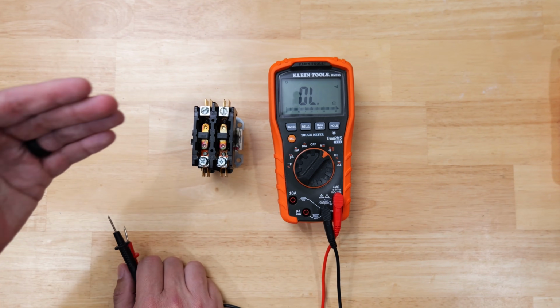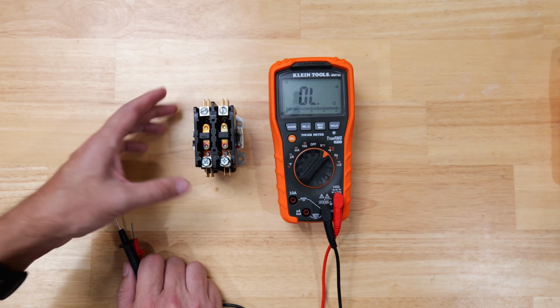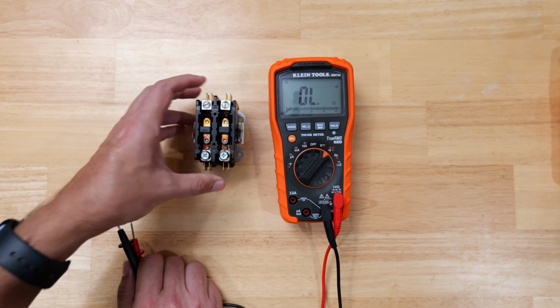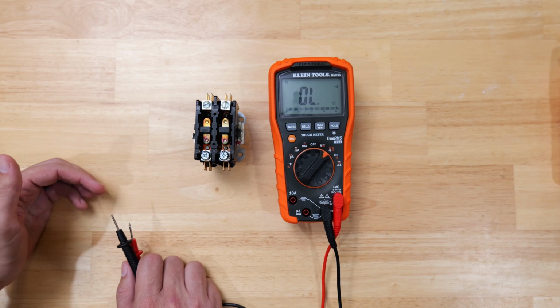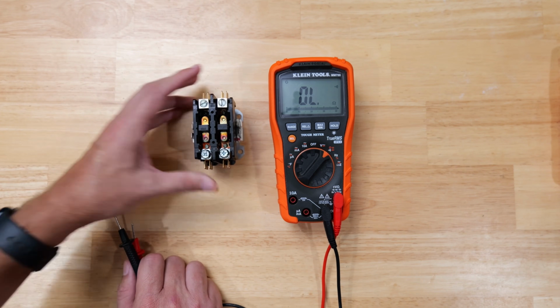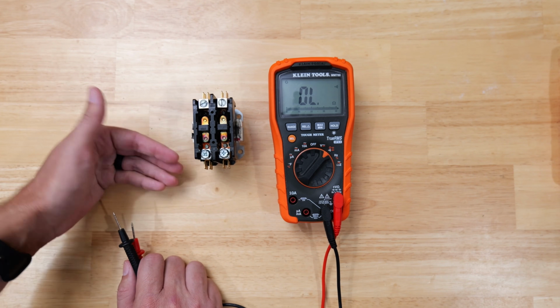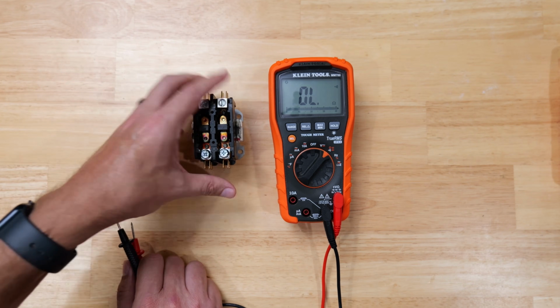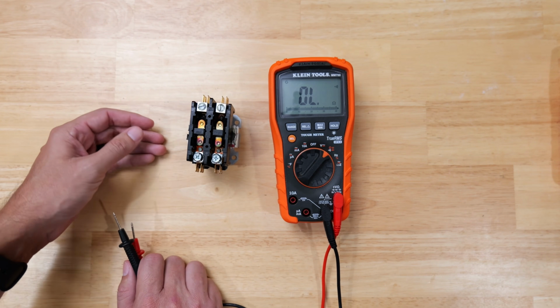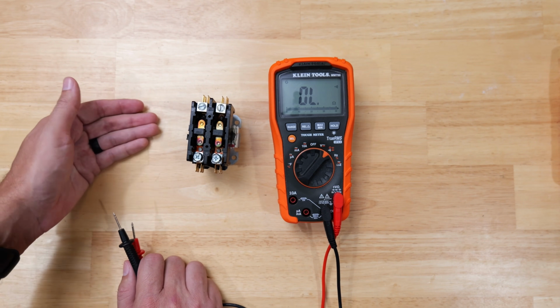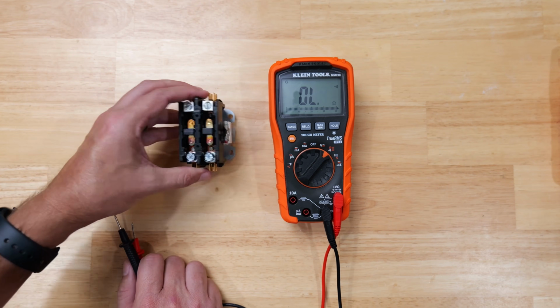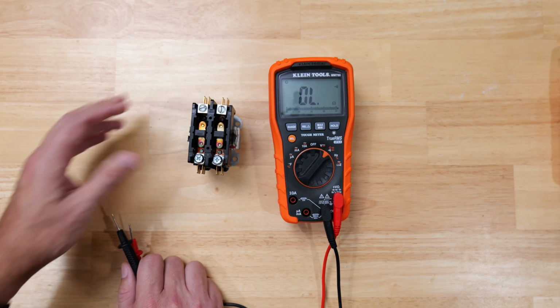For an AC contactor, that means the coil on the back is still in very good condition. Around 10 ohms is typical, though it varies by contactor — smaller ones have smaller coils, leading to more resistance. That's where the data sheet comes in handy. But as long as I'm seeing around 10 ohms, even up to about 20 ohms, I know the coil is good.